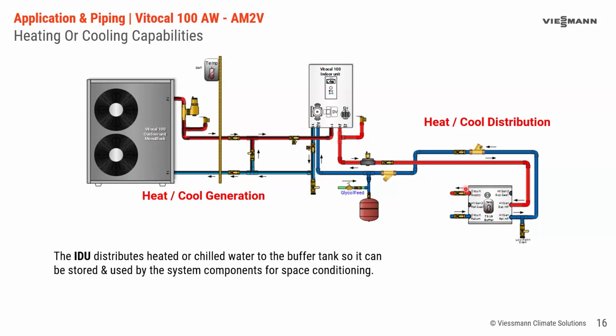So either chilled water or hot water, depending on how you're going to configure the system and what your control is set for in that particular day. It's either going to be chilled water or hot water. And the idea is this is a volume or a reservoir of energy that's there, so the heat pump doesn't have to deal with those small load changes that you might see in a radiator or in an air handler or whatever that's going to turn on and off in the system. And then from the system point here, these two pipe connections connect to the system, and we'll show you some examples of those later.